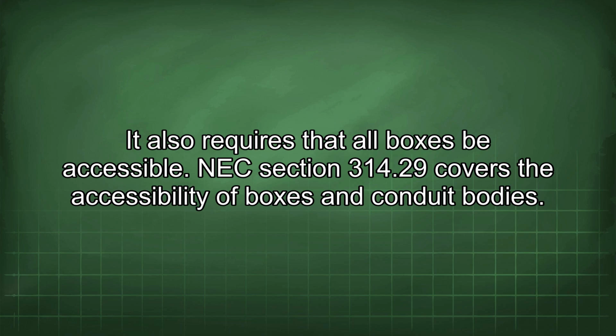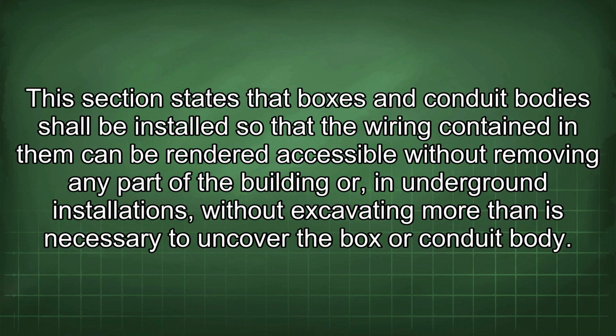NEC Section 314.29 covers the accessibility of boxes and conduit bodies. This section states that boxes and conduit bodies shall be installed so that the wiring contained in them can be rendered accessible without removing any part of the building or, in underground installations, without excavating more than is necessary to uncover the box or conduit body.